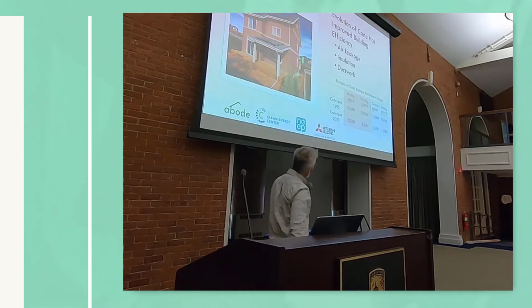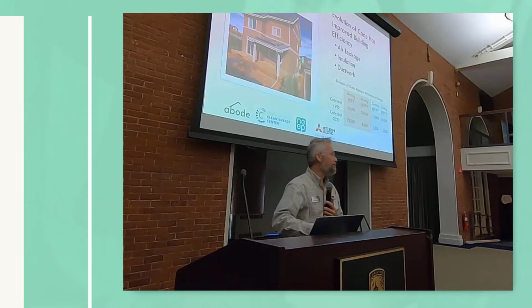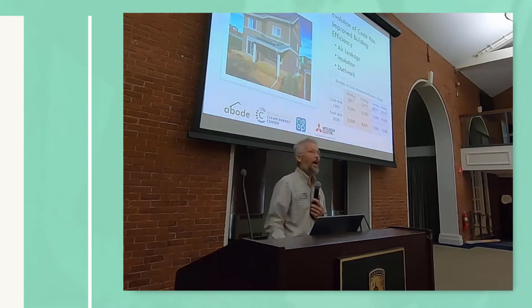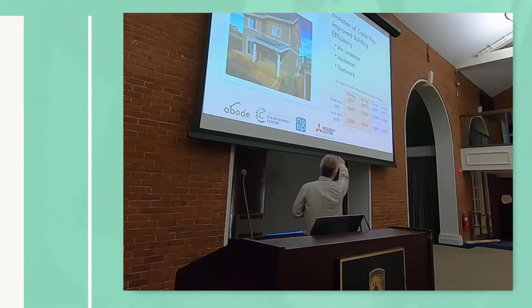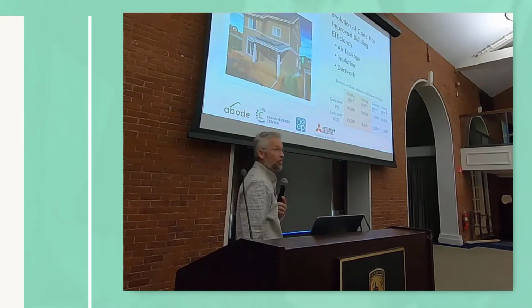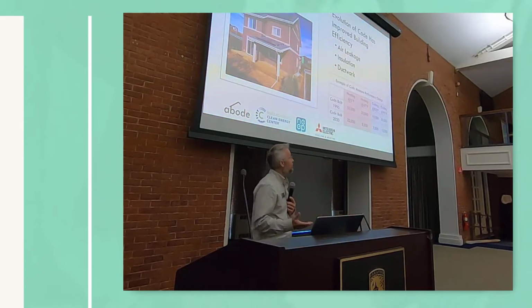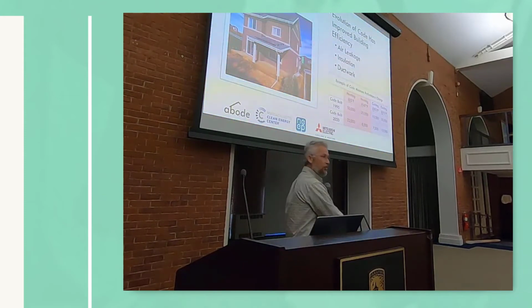But a home that has a peak of 50,000 BTUs, if it was on oil, is something like 700 gallons of oil equivalent over the course of the entire season, right? Or maybe like 900 gallons of propane. And so that same size house built to the code that's anticipated for next year at design load will be 20,000 BTUs. Now that same home, the same looking home, is just tighter and better insulated. That's going to be more like 300 gallons of oil. That's the kind of efficiency gains that we've seen.